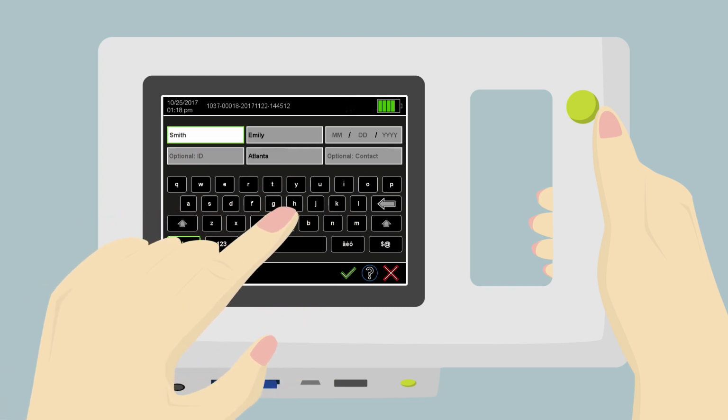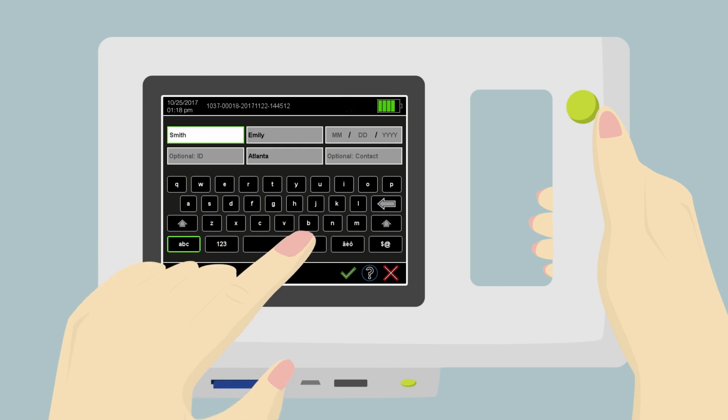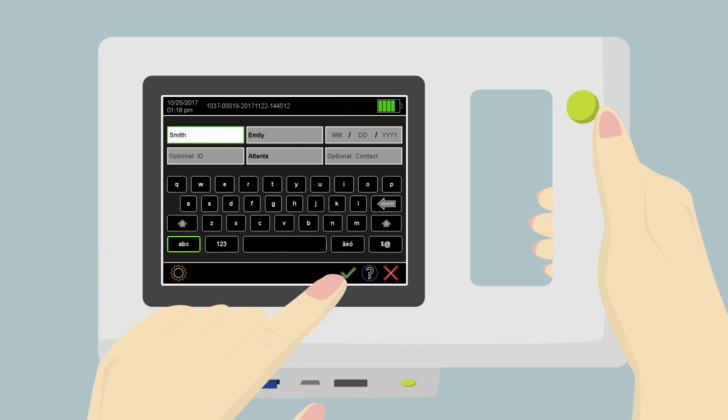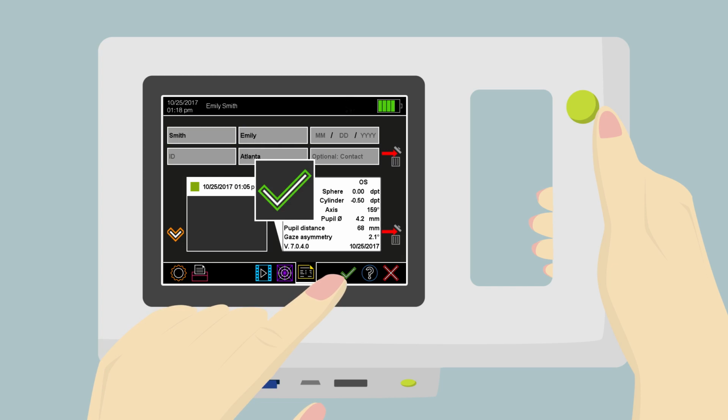In the plusoptiX A12R model, a single line to enter individual patient data will be displayed. This data cannot be saved to the patient database, but will be shown on all printouts for this measurement. Touch the green check mark in the navigation bar to confirm your entry. For an anonymous measurement, touch the green check mark without entering patient data. Instead of the patient's name or ID, an automatically assigned rolling number will be used.